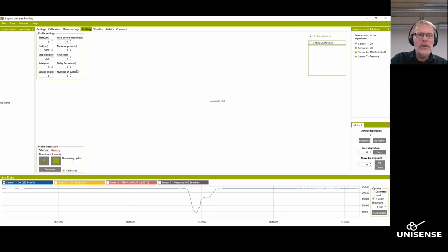And I think for this sensor, 5 seconds is okay. It's probably a little bit on the short side, but we'll see. The measure period is the period it waits after reaching a position before it takes the measurement, that is the period that it analyzes. So after 5 seconds, it will measure for 1 second. That is, it will measure about 20 data points, take the average of those and save that together with the standard deviation of these data points.